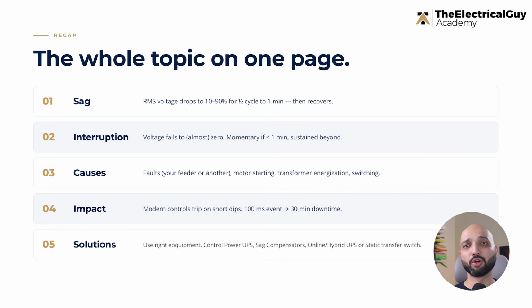All right, so now let's summarize the concepts clearly. Voltage sag is a short-duration drop in RMS voltage, less than 1 minute. Voltage interruption is complete or near-complete loss of voltage for less than 1 minute. The most common cause is a fault on the power system. The fault may be on your feeder, a parallel feeder, or even the transmission system. Other causes include large motor starting, transformer energization, sudden heavy loading, and switching events.